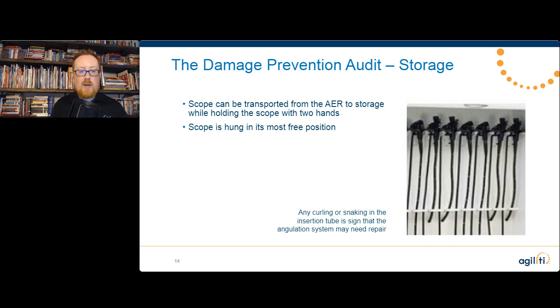And then, of course, making sure that the scope can be transported from that AER to the storage while holding the scope with two hands. And we want to make sure that that scope is being hung in its most free position. When you see scopes kind of doing this little measure right here, where they do a little bit of that, we call that snaking. That means your angulation system is getting stretched out. Those wires are pushing out against the side of the insertion tube. And when you hang a scope freely and that pressure's being pushed out, that's what it looks like, that little snaking action. And even when you see some curvature like this, that can be an indication of a problem with your tensioner system or your angulation system as well. So, just by making those simple observations, you can understand where that damage is coming from.